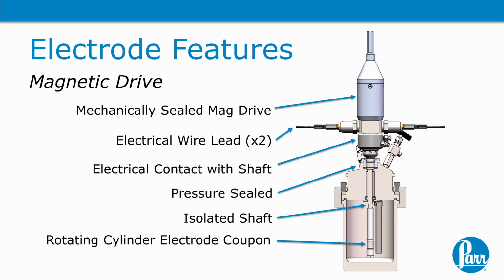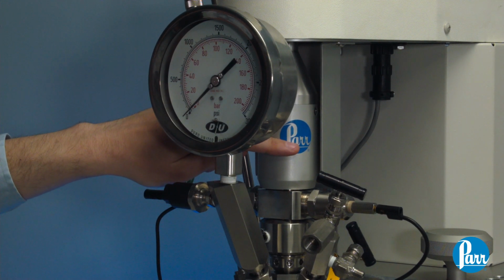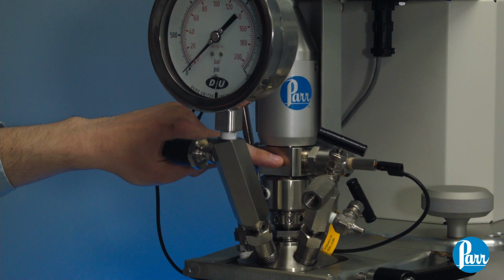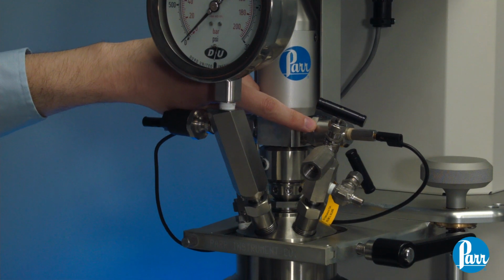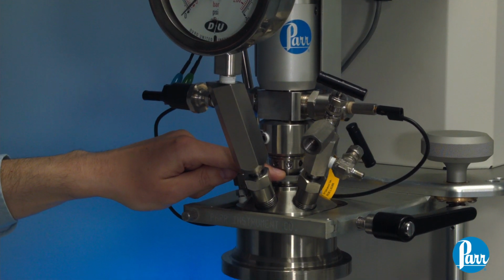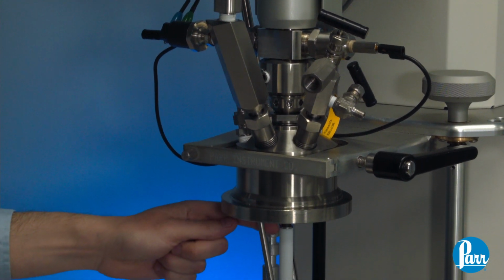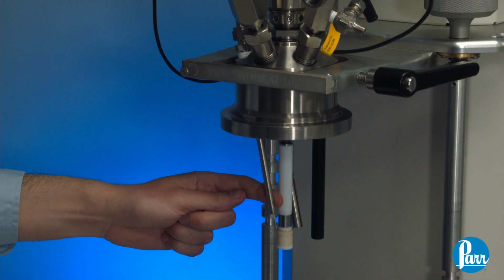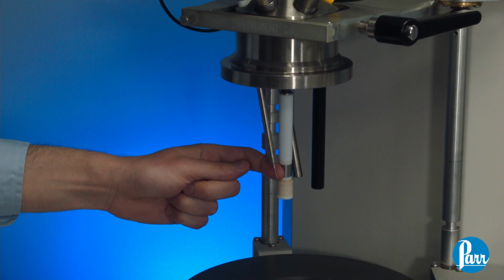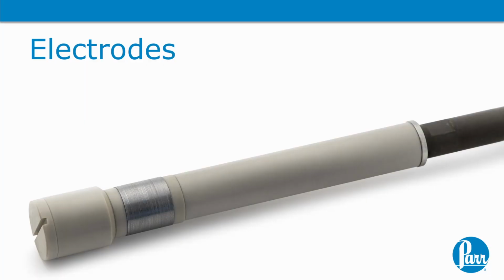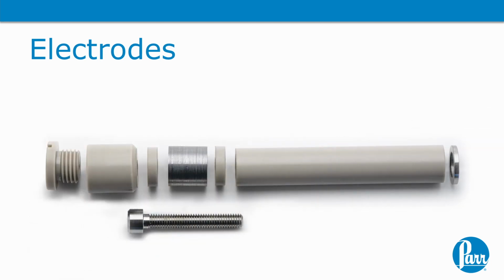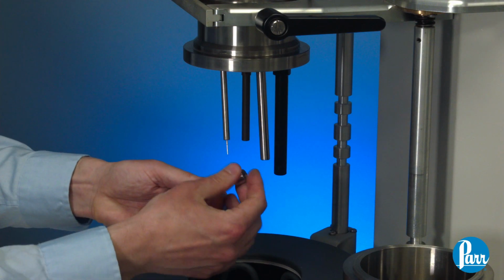Now let's talk about the heart of the instrument that makes it special, the rotating cylinder electrode design. The magnetic drive that serves as the working electrode for this system has the following design features. The wire leads make electrical contact with this shaft in the brush housing section of the magnetic drive. There are duplicate electrical wire leads to ensure proper electrical contact with the rotating shaft. The magnetic drive is pressure sealed to the fixed head of the pressure cell. A coated isolated shaft makes direct contact with the rotating cylinder coupon inside the working electrode isolation assembly. The working electrode isolation assembly consists of PEEK components that allow the machined 1/2 inch OD rotating cylinder coupon to be mounted for corrosion testing.